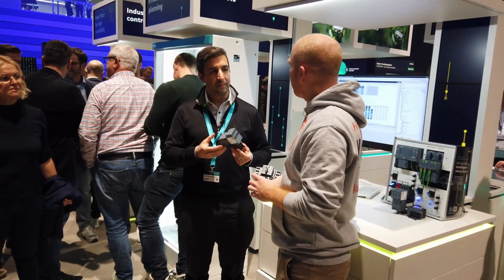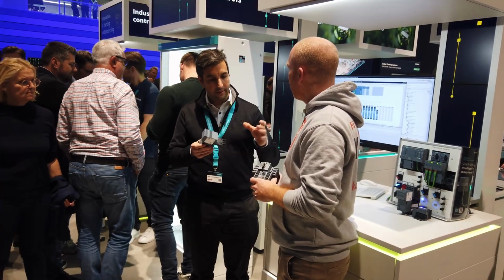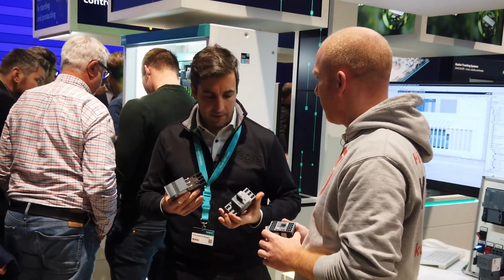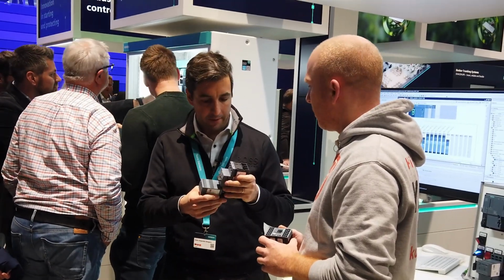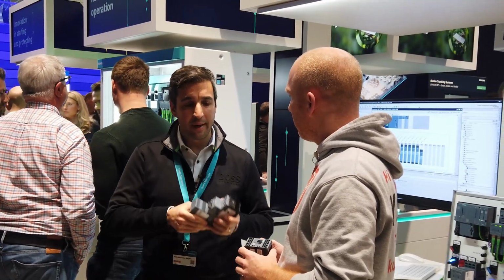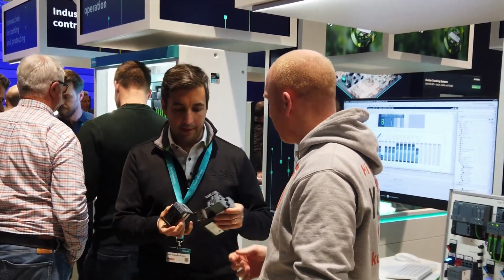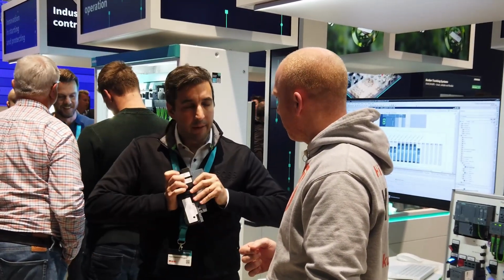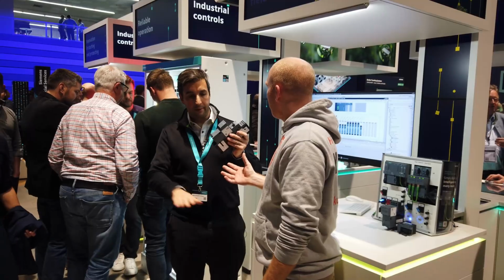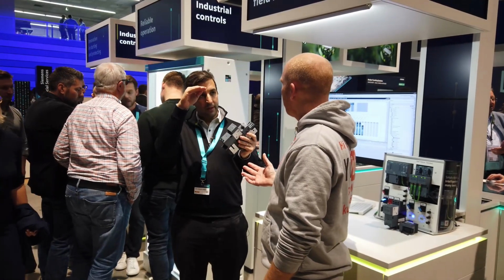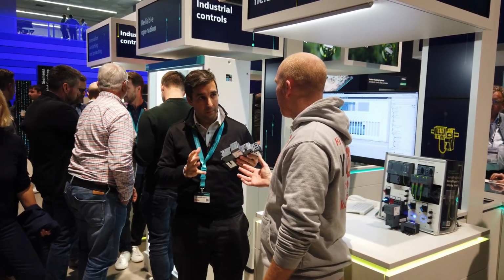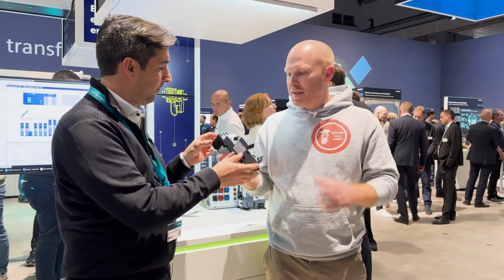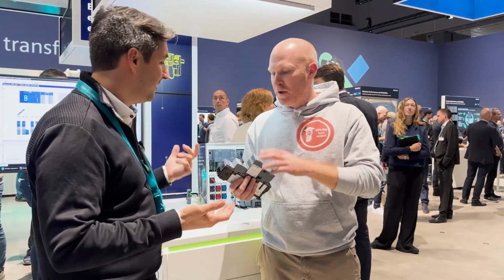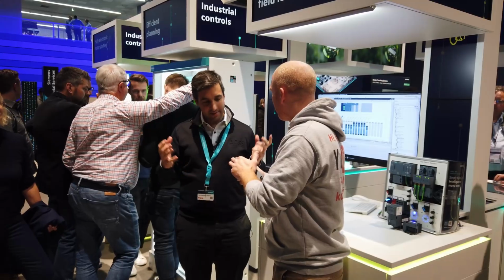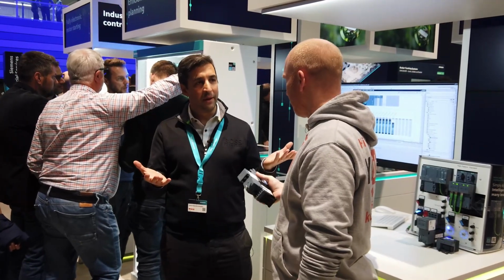Well, this product is marrying or joining this standard circuit breaker and the standard contactor that we know from forever, right? And make it transparent for the complete application. And in this way, also making a full connectivity between the field level to the automation level in one system together with SIMATIC. And I see the assembling is quite easy. Yeah. Because of the push-in technology. It's just push in and you have the complete feeder there.